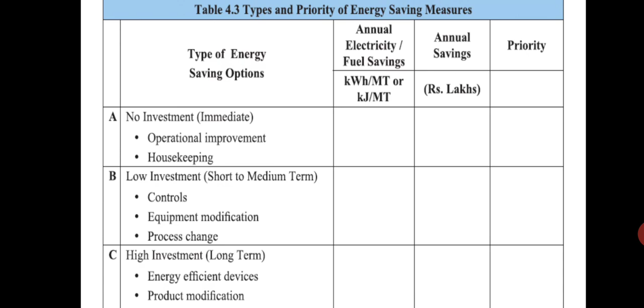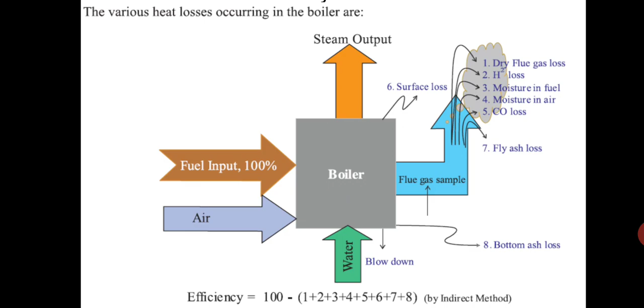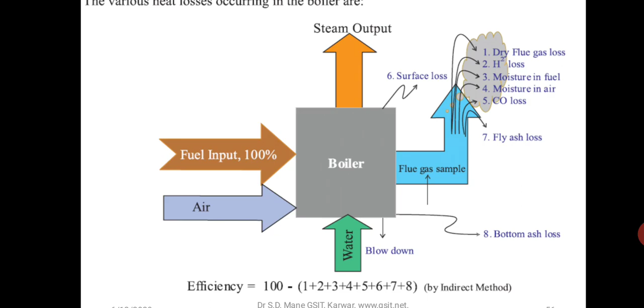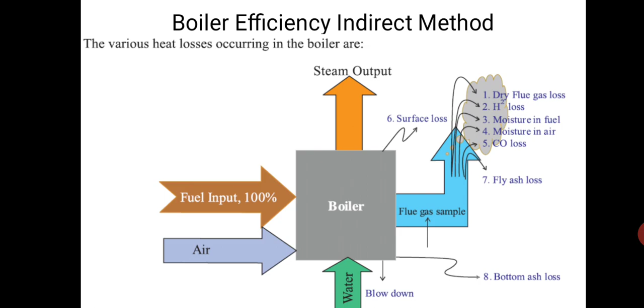Just as a mechanical engineer, I think you'll be interested, you study the boilers. I wanted to show one small picture, like what is the efficiency of a boiler. Here on the boiler, on the left side you can see fuel input and air is supplied. Then water is supplied and goes out as steam. The blue is the flue gases, which contain dry flue gas loss, hydrogen loss, moisture in fuel, moisture in air, carbon monoxide loss, fly ash loss, as well as the surface loss, bottom ash loss, as well as blow down. So when you take a detailed study of boiler efficiency, you will study all these losses, 1, 2, 3, 4, 5, 6, 7, 8, and subtract them from 100. This will give the detailed efficiency of the boiler by the indirect method.